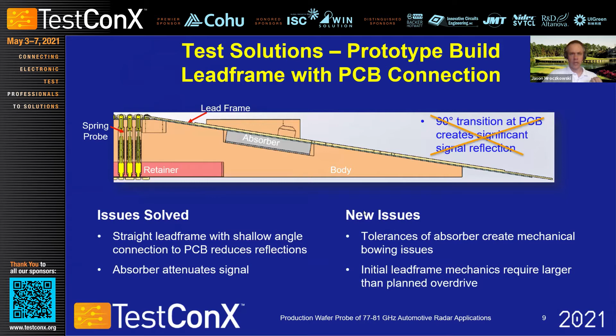The other thing you notice is that, if you look at the profile, these are angled lead frames. So they angle up at about an 8 or 9 degree angle down to the board where they make contact. They're approximately 25 millimeters long. So you do have to find space for these in the probe head and on the PCB. It can impact the ability to put componentry in and, of course, route traces.